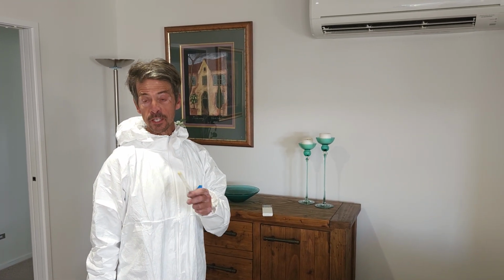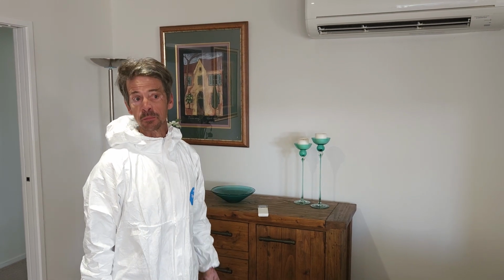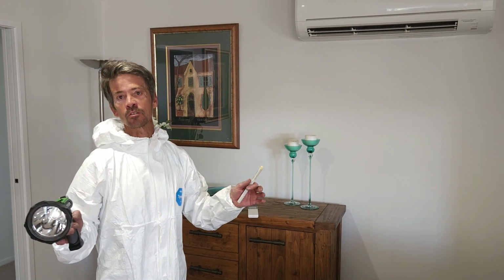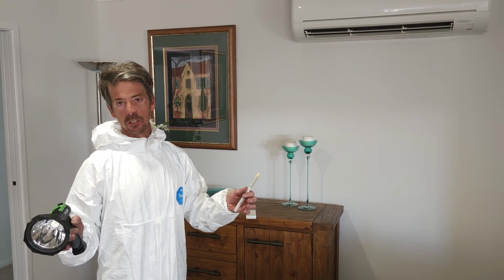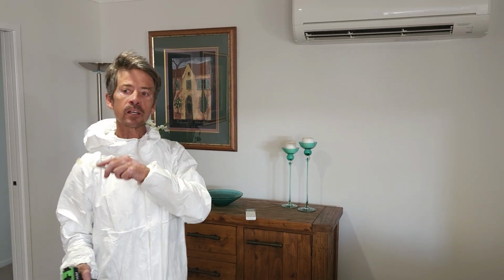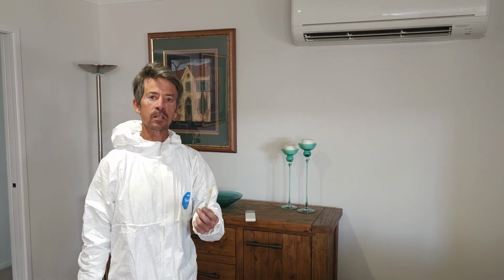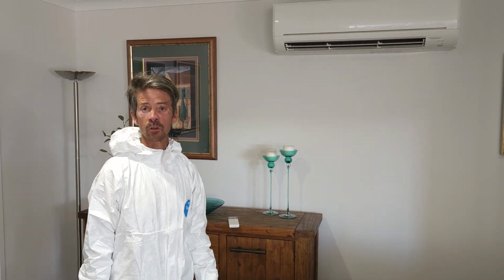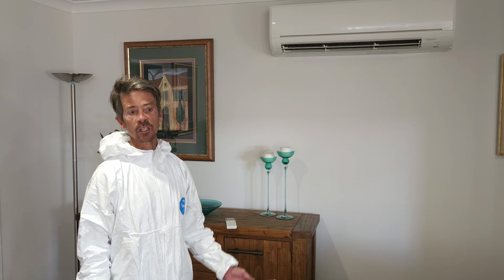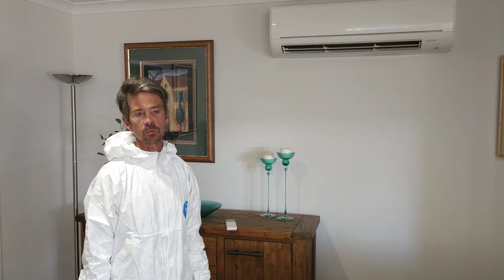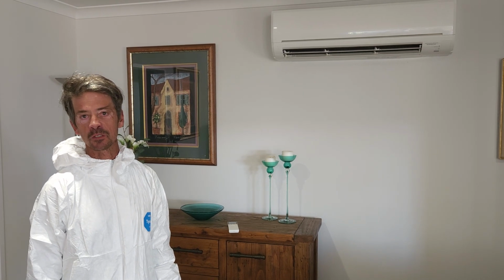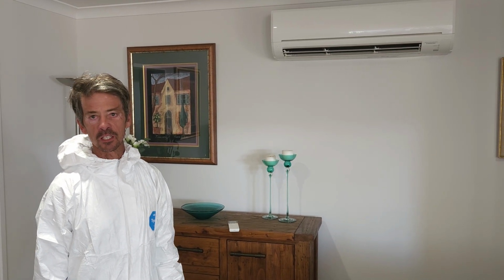Before we do any testing, we make the occupant shut the house for a minimum of 24 hours to figure out what's happening within their house humidity-wise. We'd take humidities in every room to see if there are any differences, a potential area for water ingress or higher humidity in a certain room, which gives me more idea of what's happening, and to see if there's any good passive ventilation, which in new houses like this tends not to be very good because they're so airtight now.